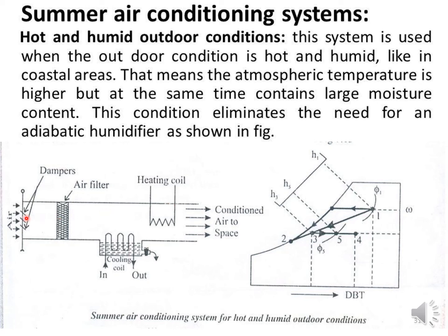So similarly here, air enters the damper. The damper controls the flow of air, and filters filter the impurities. From here, as soon as it passes through this space, what will the air cooling coil do? It will cool the air by taking the temperature of that air as it is passing through this cooling coil. So as soon as it comes out of this cooling coil, its temperature is reduced. Suppose it is 25 here, I require 18. So based on that, the cooling coil needs to be designed. So as soon as the output air comes here, it will be around 18 degrees Celsius.